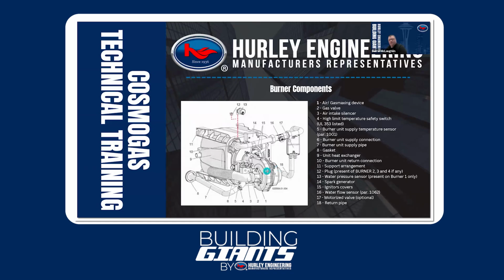Moving on, this is the internals, the heat exchanger and burner combination. You can see this is our gas valve here, and this is our Venturi or pre-mixing device. This is a pre-mix burner. So over here would be our motorized valve if we have that option included. Right above it here, number 16 is a flow sensor. So each one of these heat exchangers, they're low mass. We want to protect them, make sure they have flow all the time. They do have flow sensors.